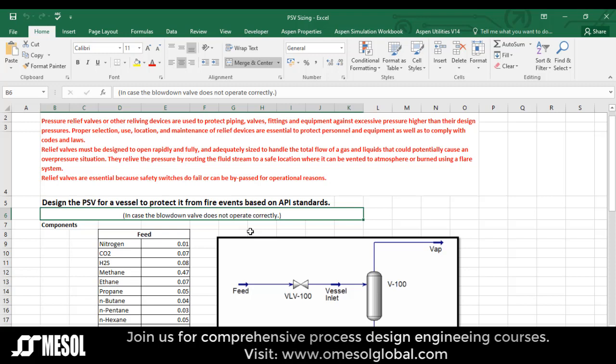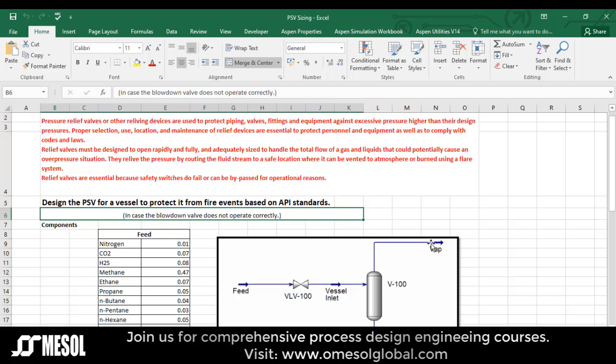In this particular case the blowdown valve does not operate correctly, which means the total flow will pass through the pressure relief valve.